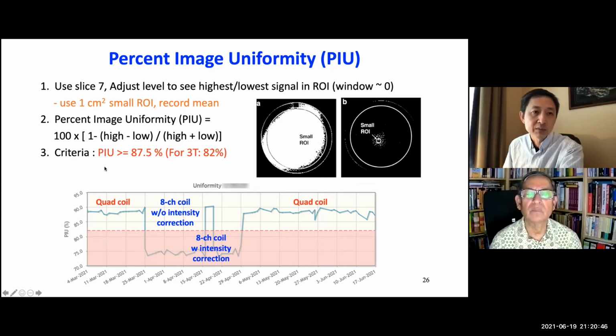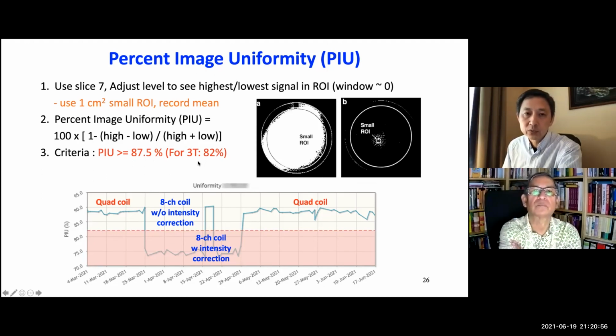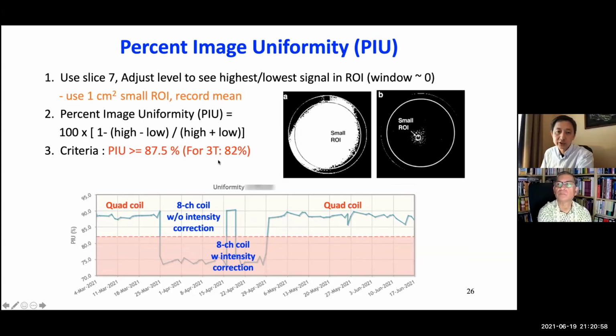So the ACR requirement is that the image uniformity should be more than 87.5% for all scanners. For 3T, uniformity can be worse because of the dielectric effect. So the criterion is 82% for 3T. So here shows an example.